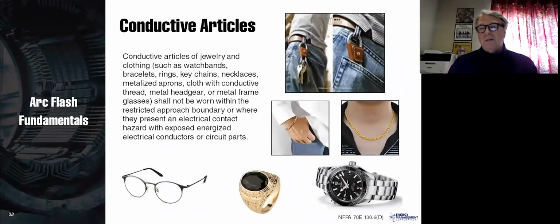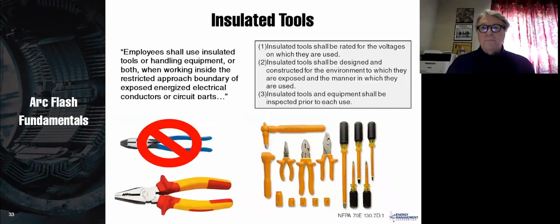Conductive articles, I think this is kind of obvious, but they want to make sure you don't wear conductive articles where that could increase the chance of an arc flash. And normally you're not going to have this kind of stuff, but you know, if you're walking around like this guy with some keys hanging off your belt and your shirt and your pants and everything are arc rated, that's still a violation to have things that are conductive on the outside of your body there.